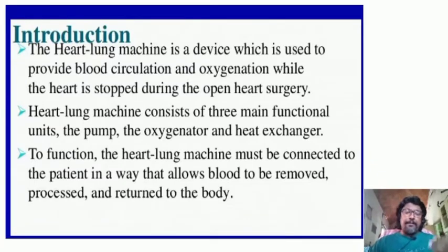At the same time, the surgeon or the doctor can perform an operation as well, right? So this machine consists of a pump which functions as the heart, and the lungs act as an oxygenator. And of course we have to maintain the temperature as well, because the temperature of the blood is also being maintained. So that also has to be performed in the heart lung machine. So three important things in the heart lung machine.